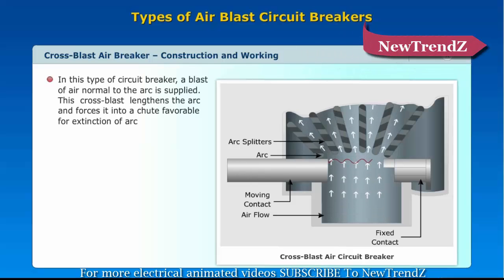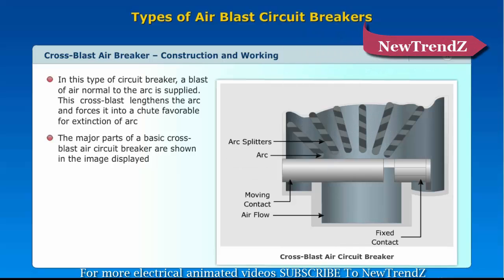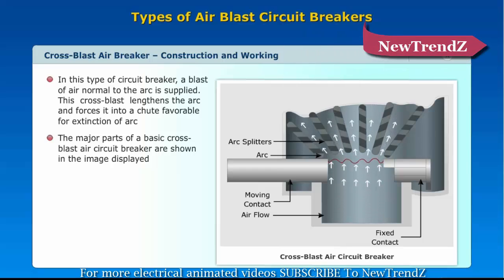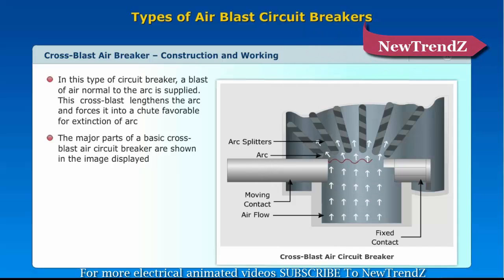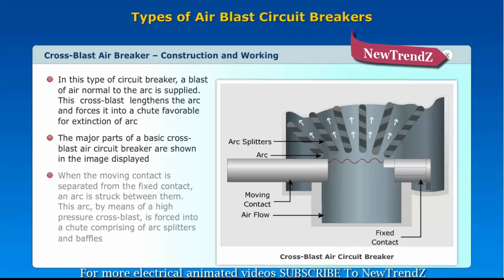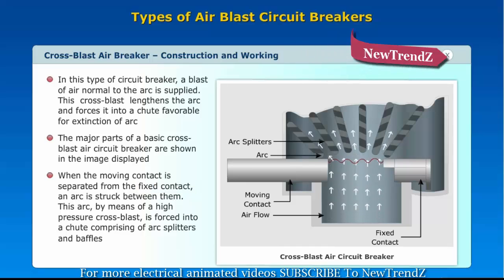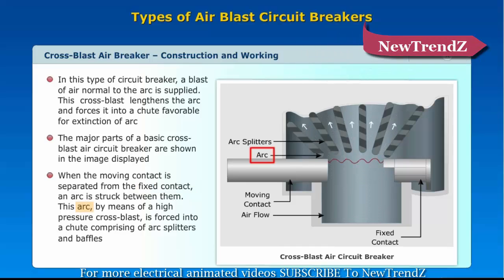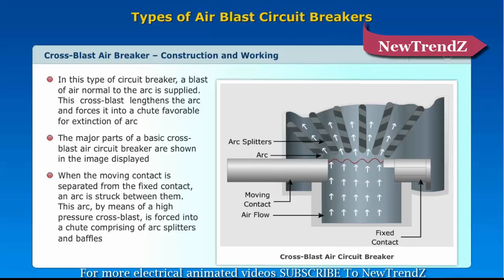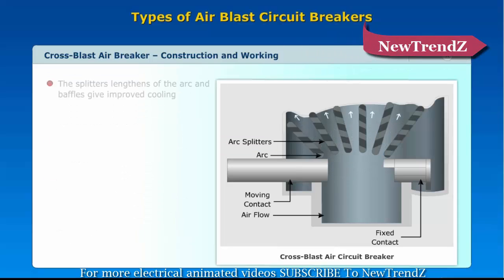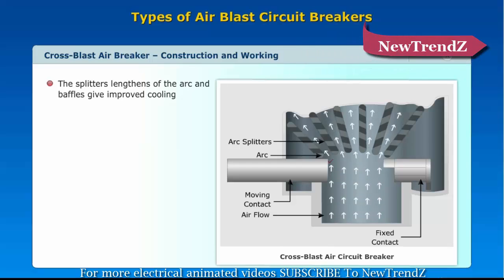In a cross blast circuit breaker, a blast of air normal to the arc is supplied. This cross blast lengthens the arc and forces it into a chute favorable for arc extinction. When the moving contact separates from the fixed contact, an arc is struck between them. This arc, by means of a high pressure cross blast, is forced into a chute comprising arc splitters and baffles.